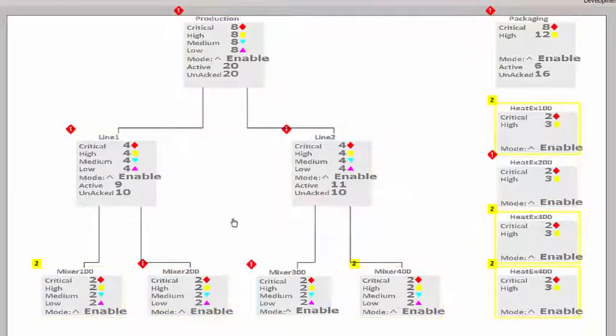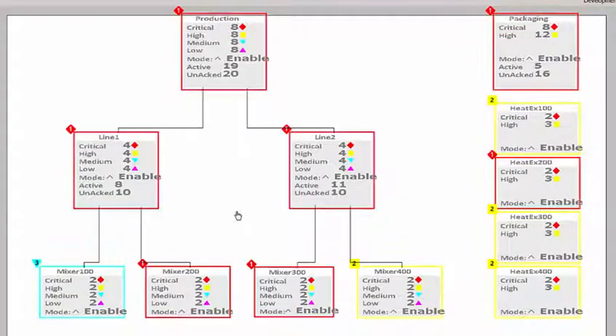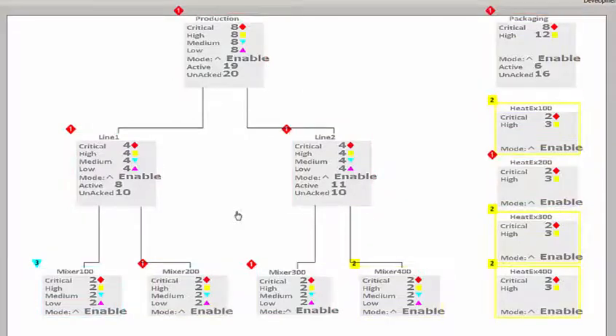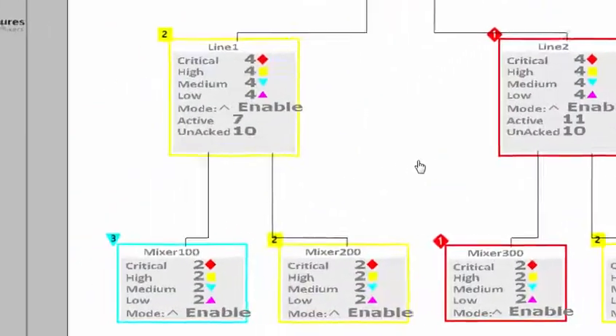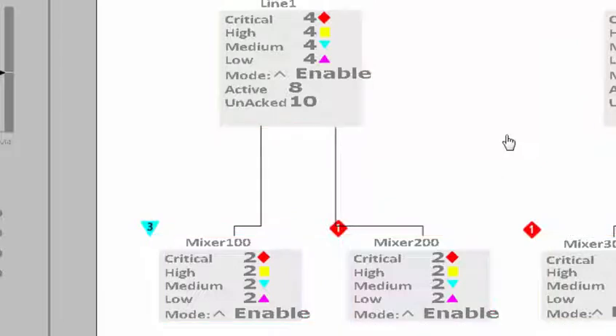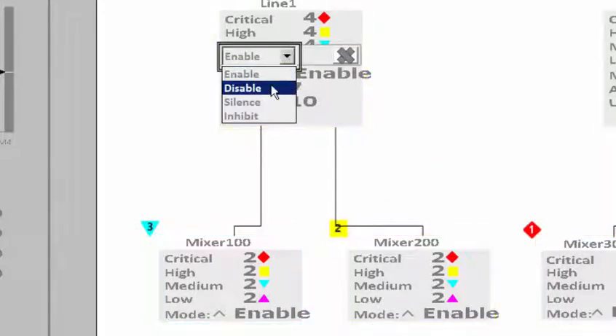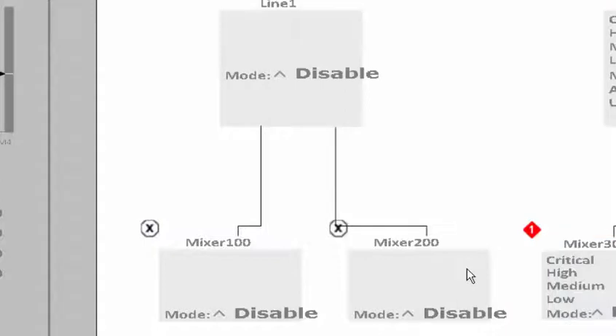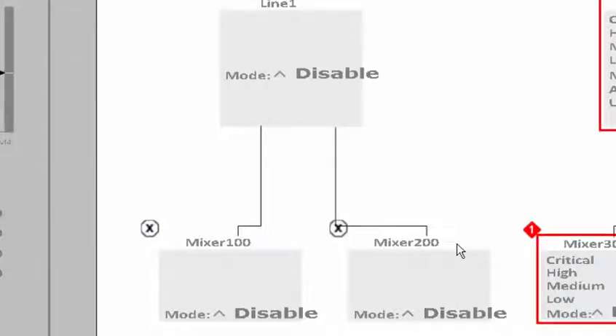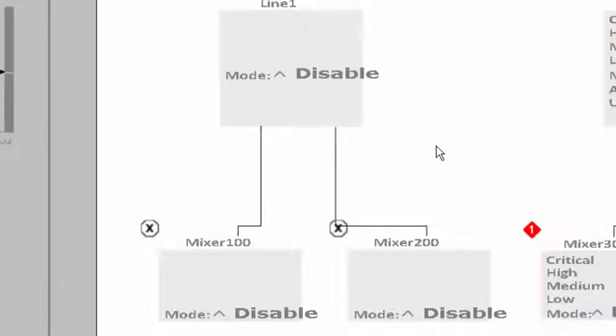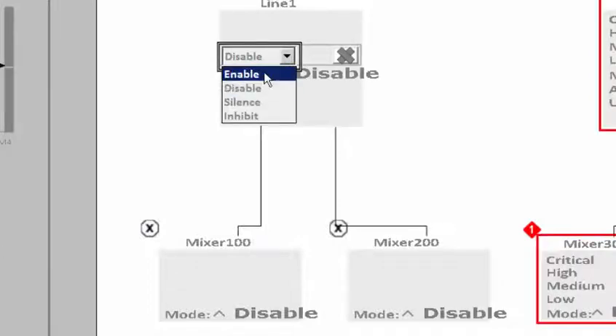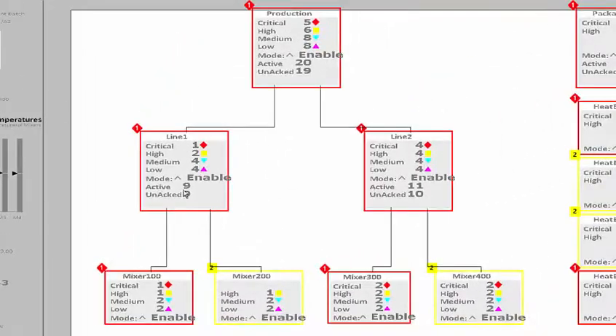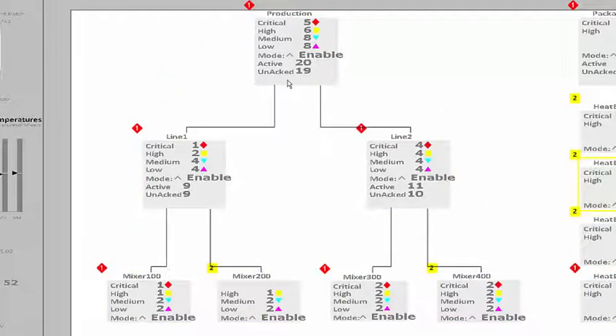As we discussed, one of the key features of a good alarm management system is the ability to not overload your operator with excess alarms. In this system, I have the ability to disable pieces of equipment or lines. So if I want to take line number one down, I can go to line number one and disable those alarms — it disables them all the way down from the line to those individual pieces of equipment, so I'm not overloaded with nuisance alarms for equipment that's not running. I can then re-enable those alarms after maintenance, and those alarm counts aggregate all the way up to the highest-level production area.